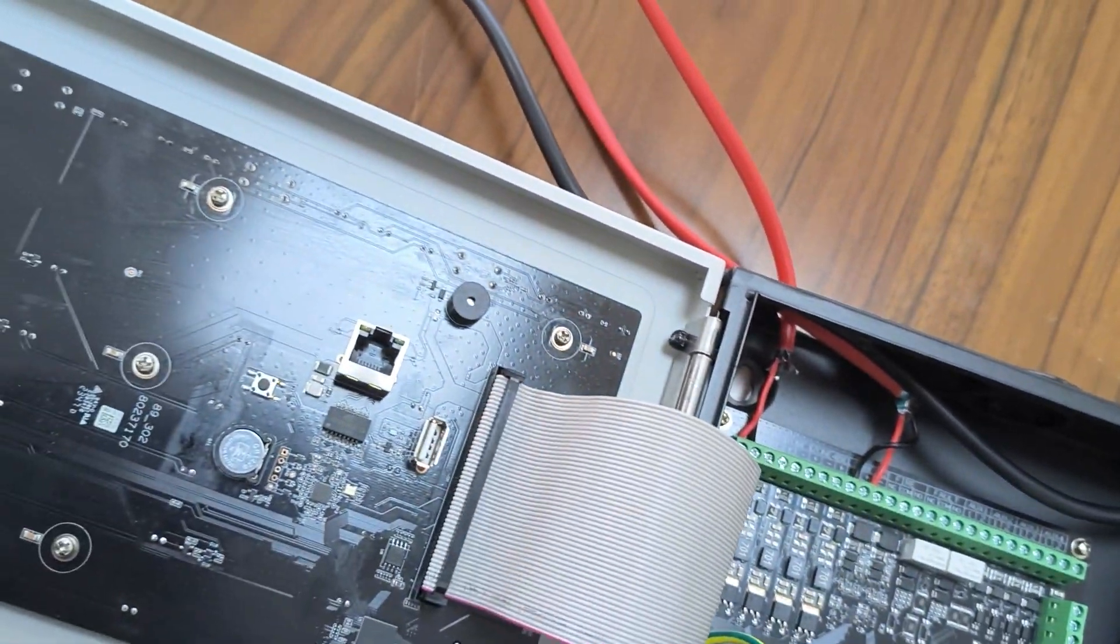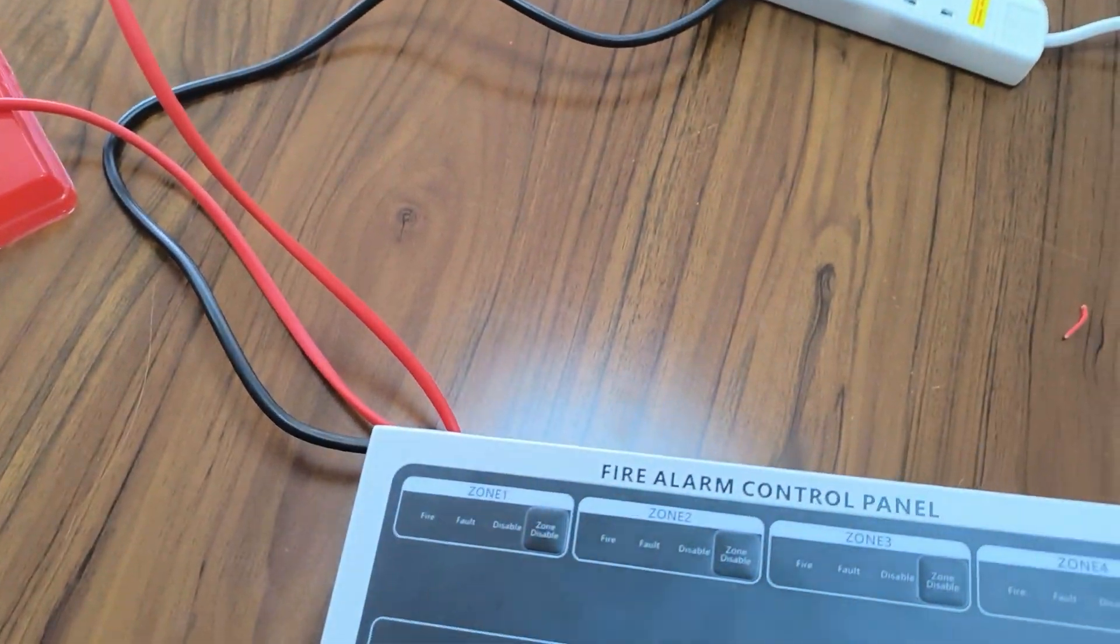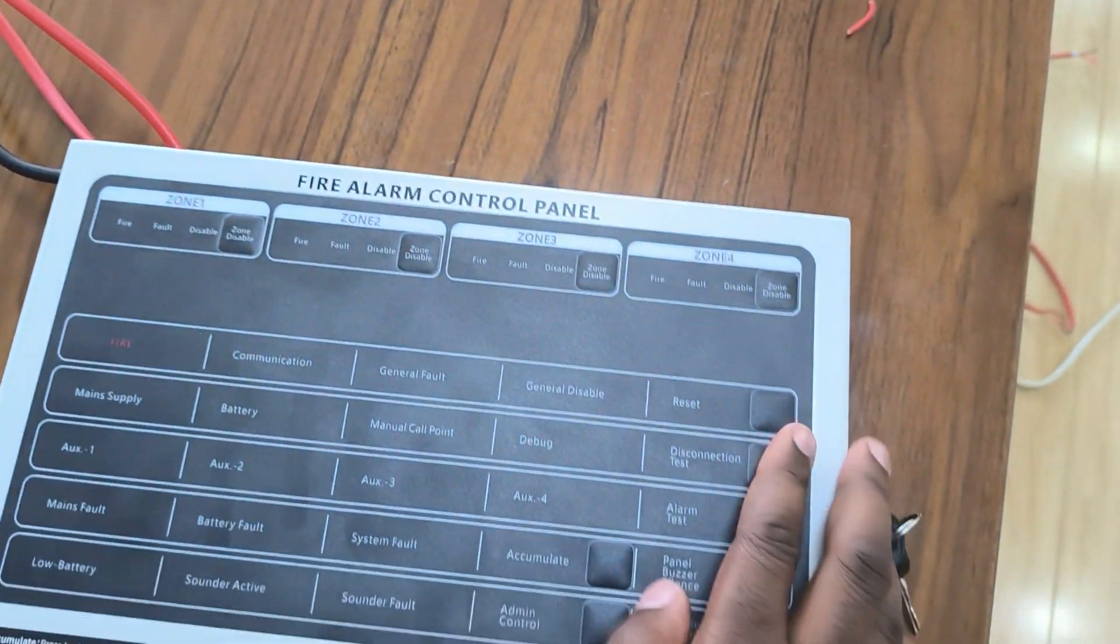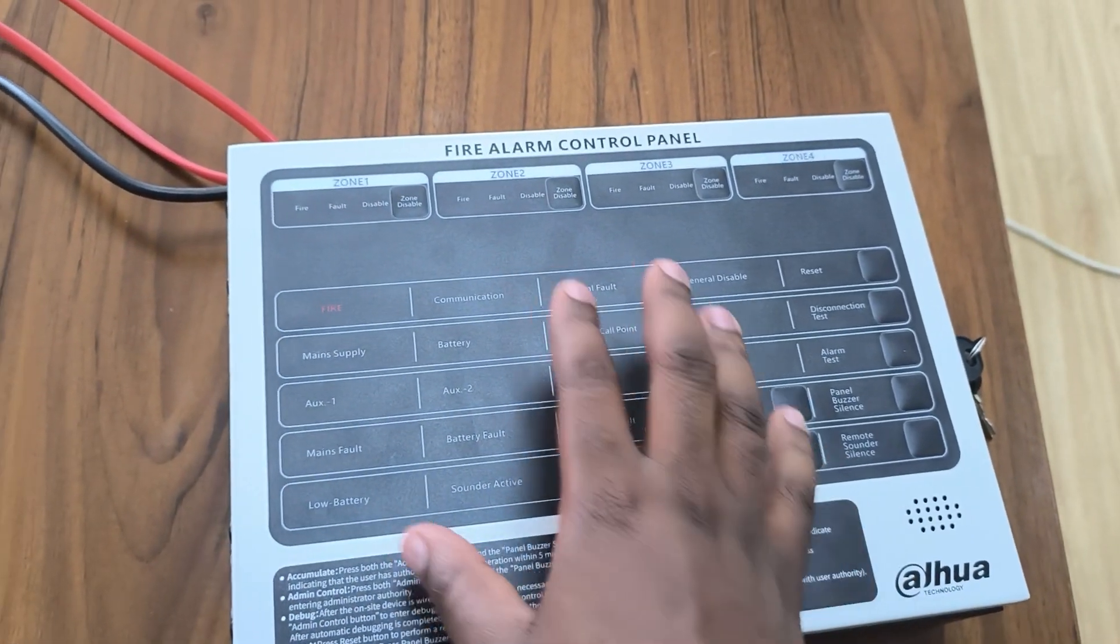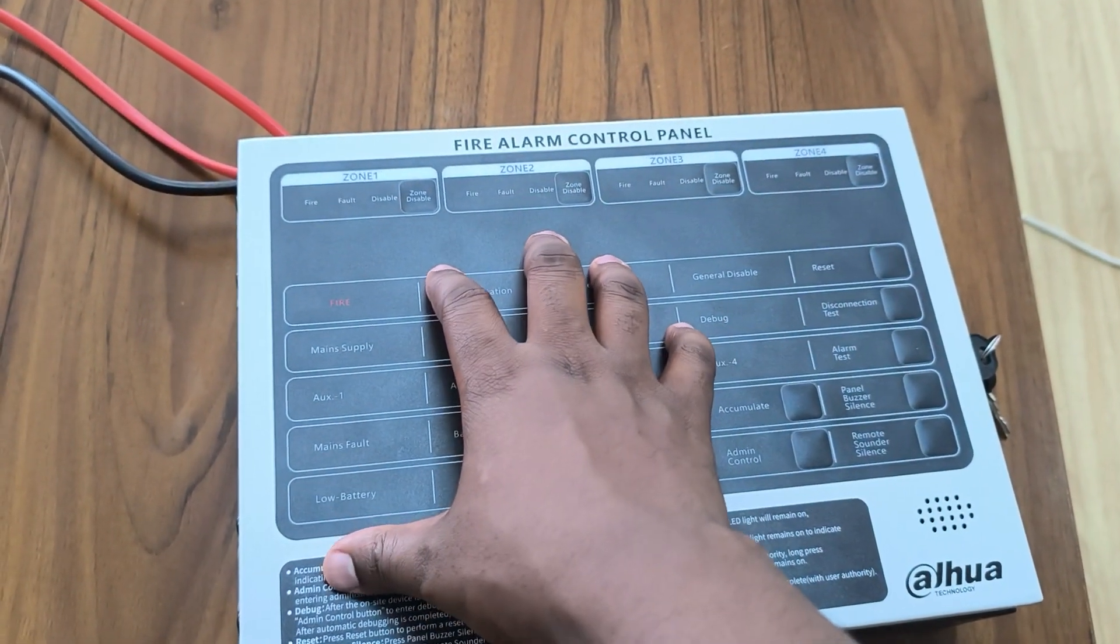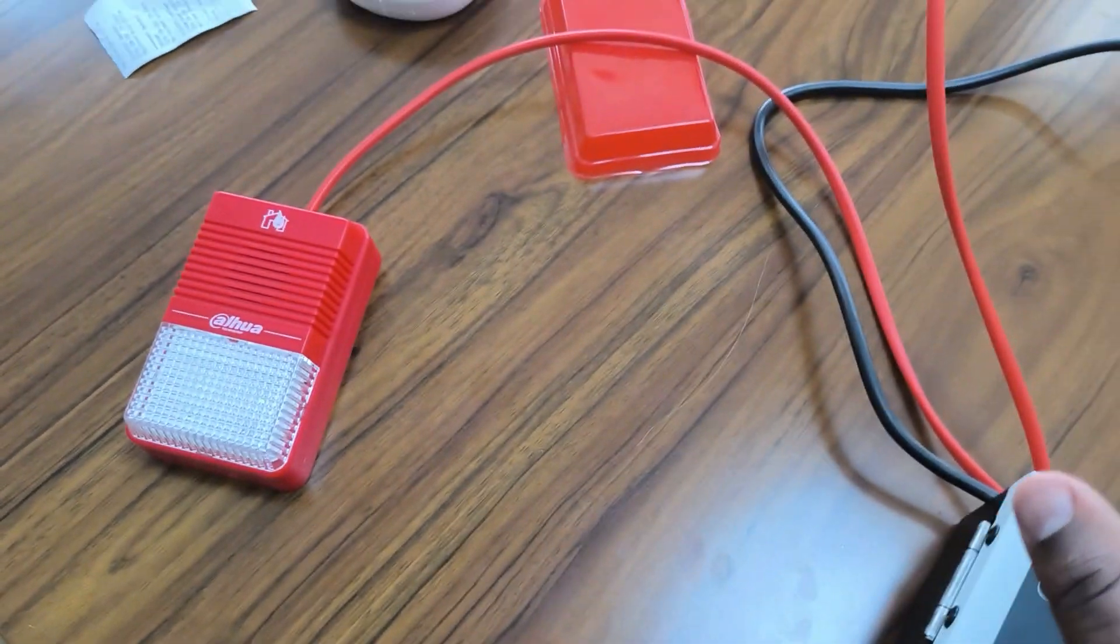So the bells, the difference between this conventional fire alarm and addressable is that in conventional fire alarm the bell system is set separately, while the addressable fire alarm we just consider them as different points.